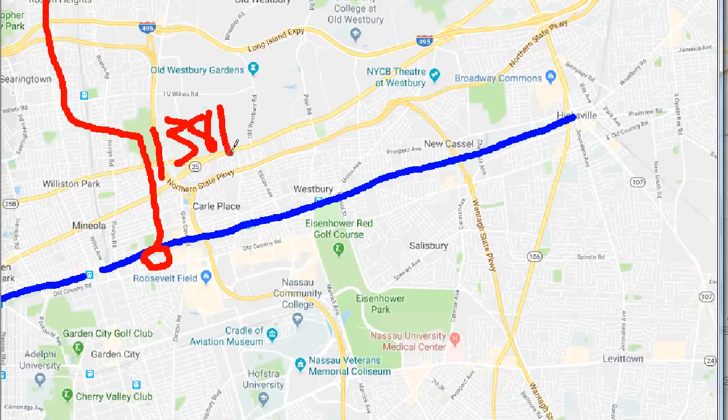All right, so a lot more power coming through, a much more major substation, and out of that substation you have the feeders that go from that substation. You'll need a new converter box, 138 kV. Usually the railroad likes to go 34.5 kV. That is usually what they feed down to on the Babylon line. You need metal poles, just like the Babylon branch has, metal poles, metal lines, and a real good high tension system for the third rail power in this corridor, which does not exist right now, and is needed.